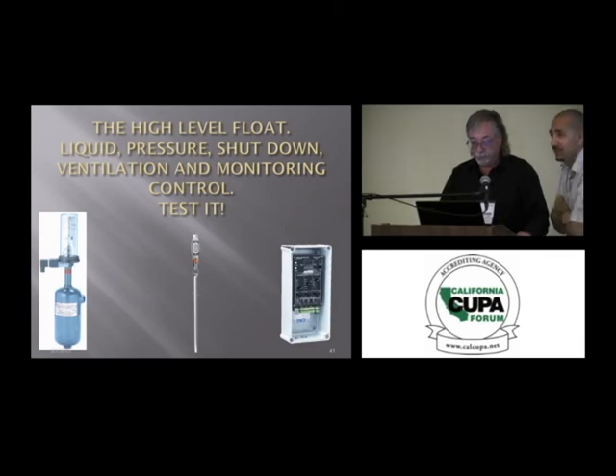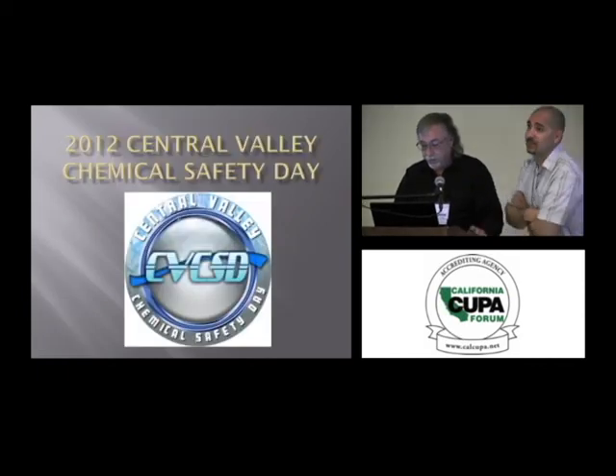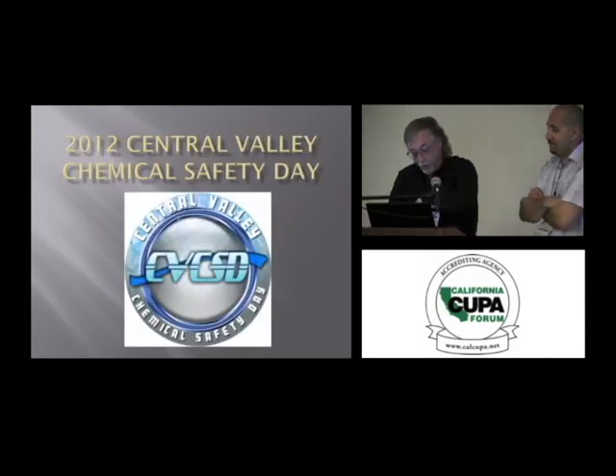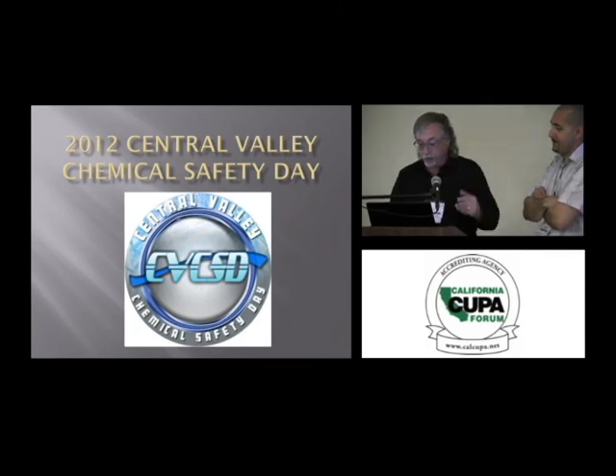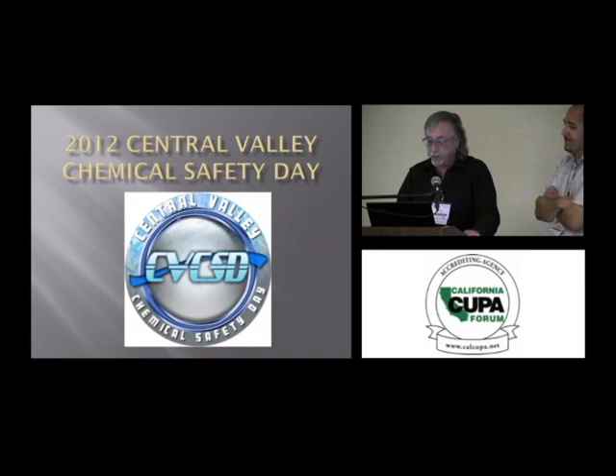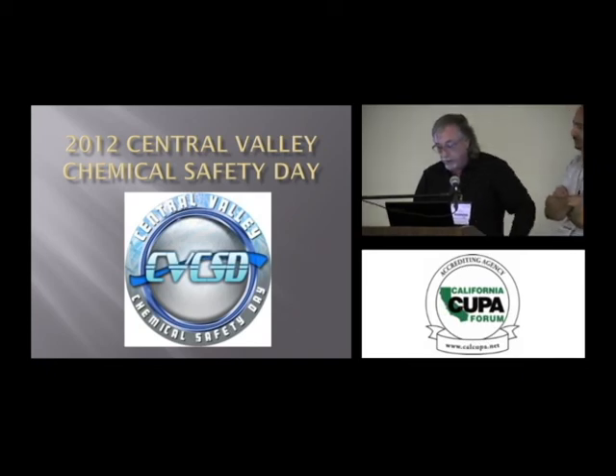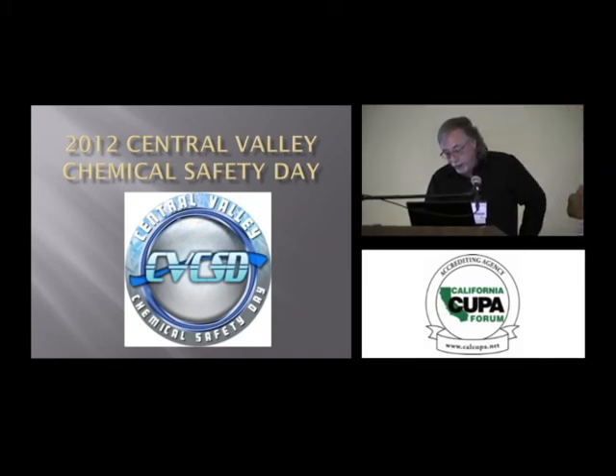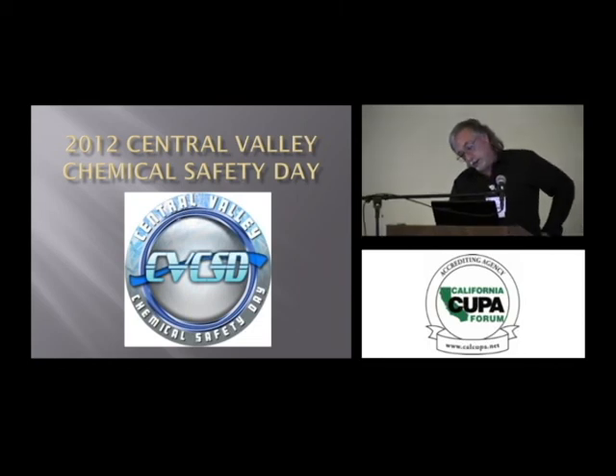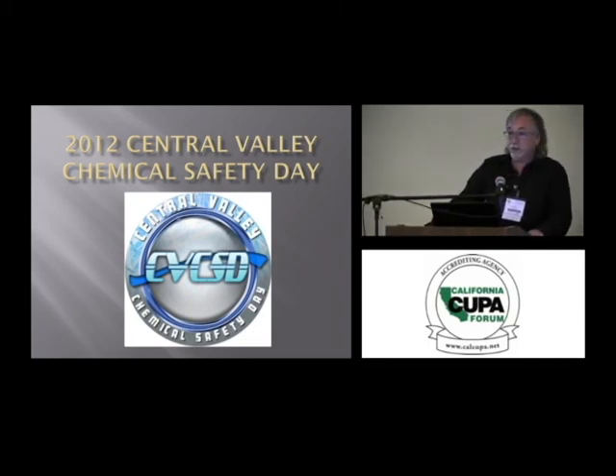Again, it's an element of the RMP, PSM, your PSSR, pre-startup safety review. We'll just go through these real quickly. We only got about 5 minutes left. I'm just going to show you some pictures. Here's a sign of vapor breakthrough where the insulators did not use enough thickness when they put the insulation on. This is at an engine room in Tulare County that they're going to fix this. I can say that because Don's a fair CUPA.